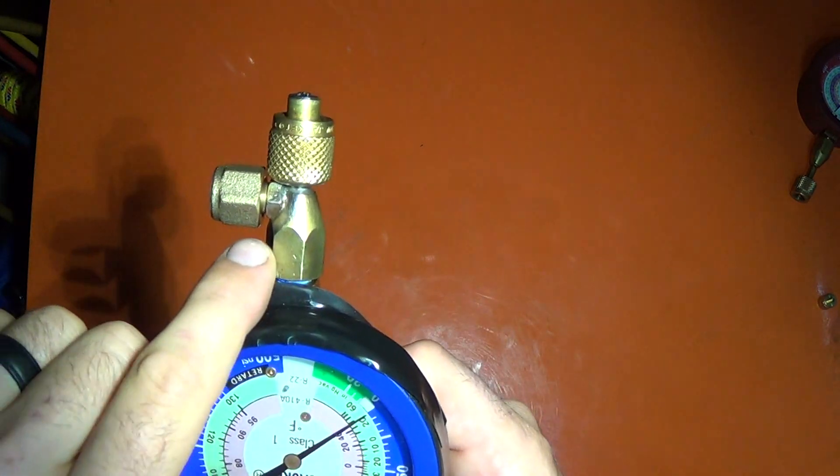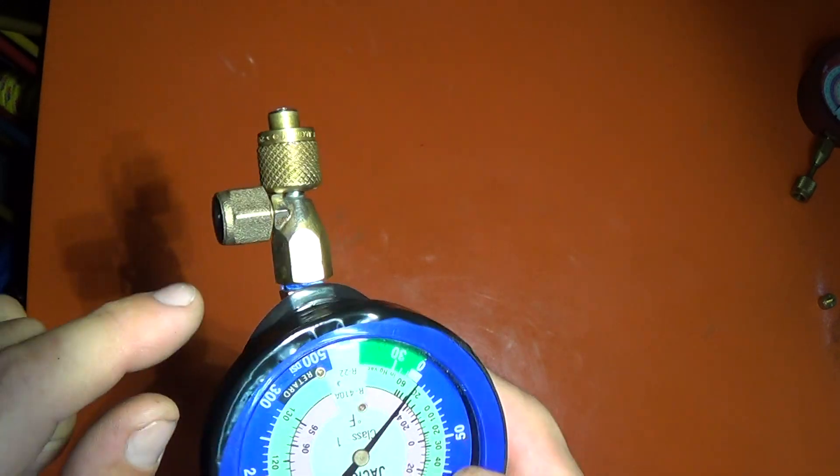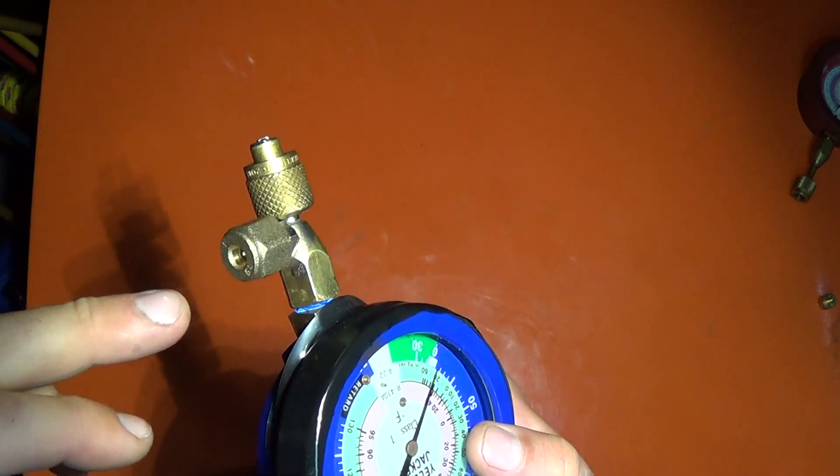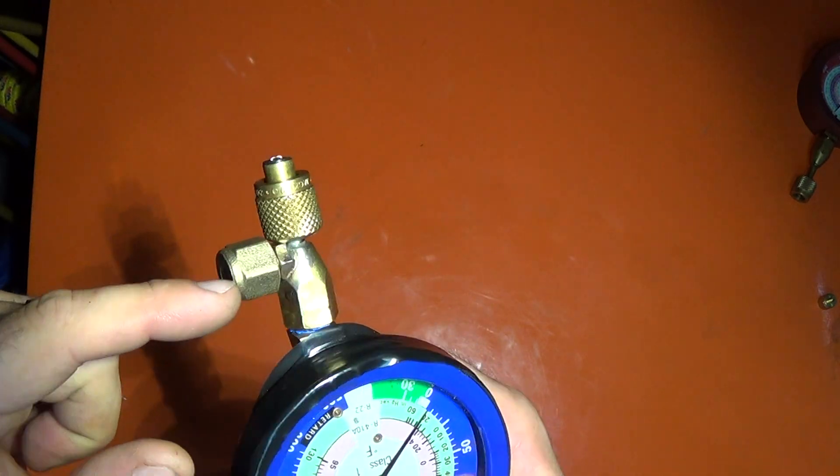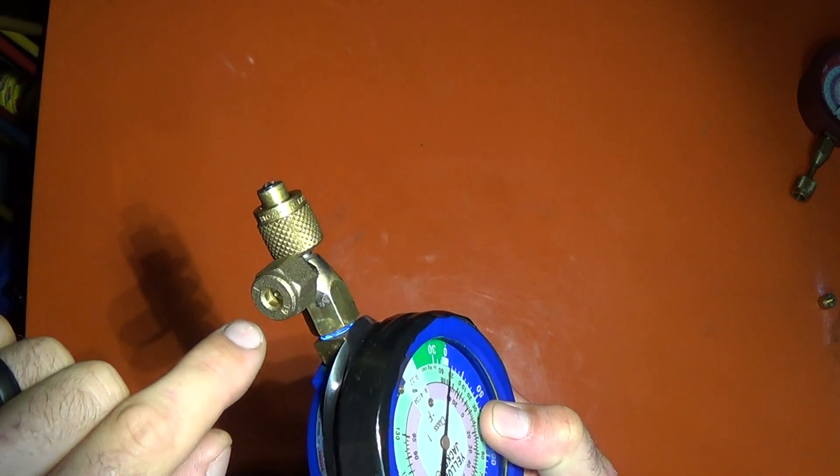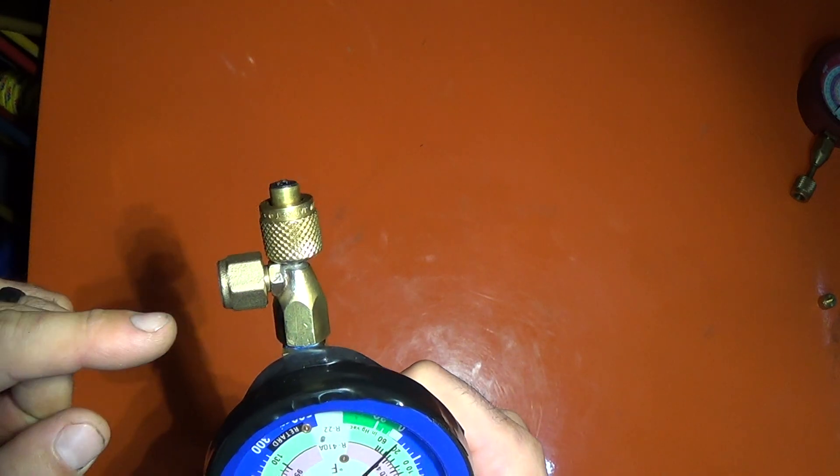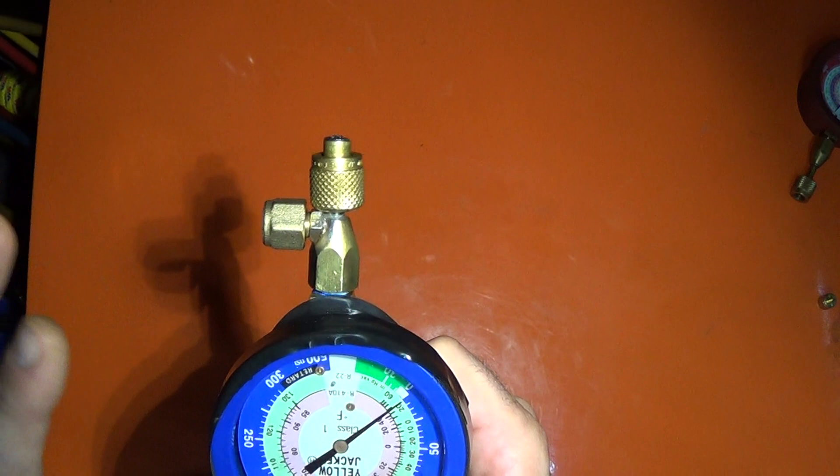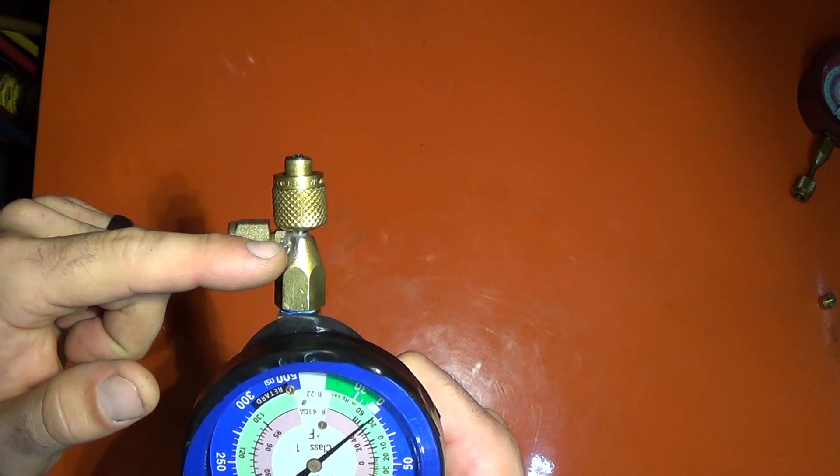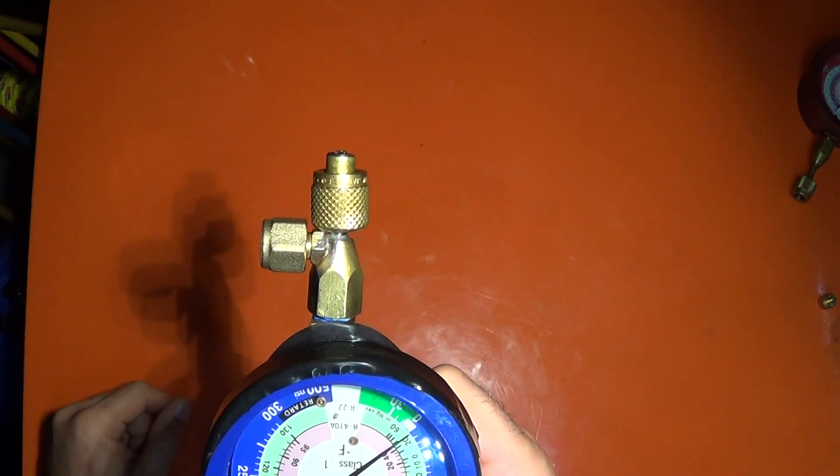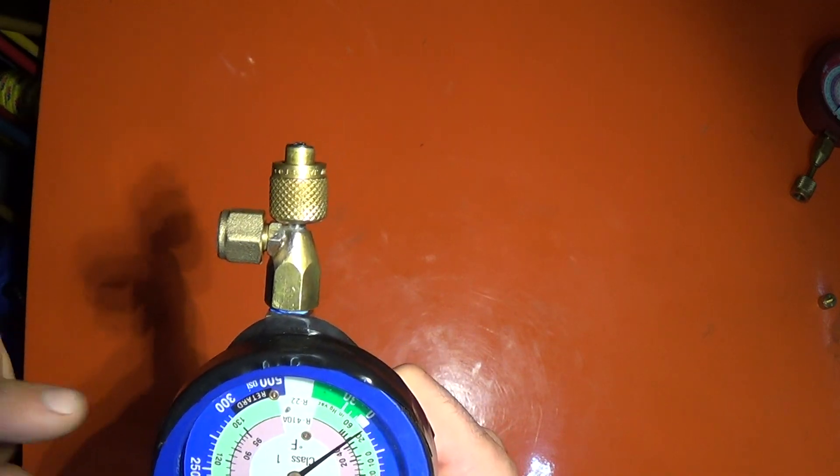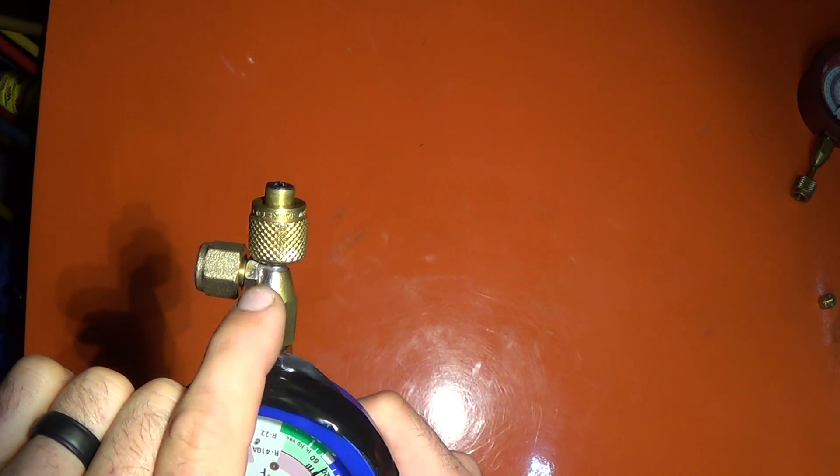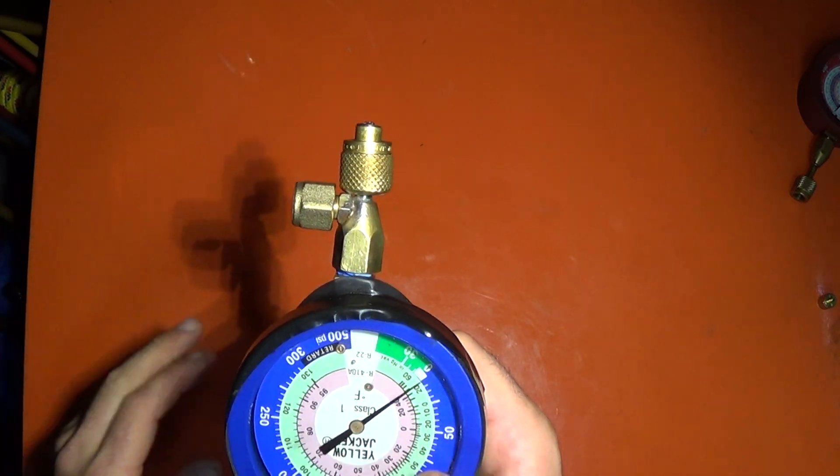So once you've got this brazed onto here, then I take, obviously you've got the core out because you're brazing. Then you take a drill bit that's small enough so you can get it in that hole. Then you drill your hole. I wouldn't drill the hole first and then try to get this lined up on the hole. Just get it brazed on there, then drill your hole through. And once you drill through, you might have to drill through this way to knock out the burrs that are in there.